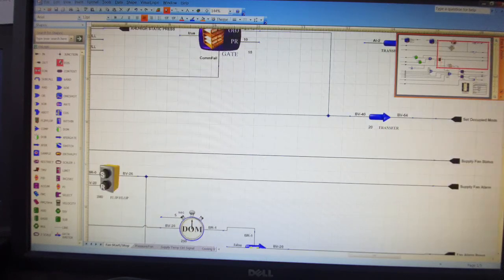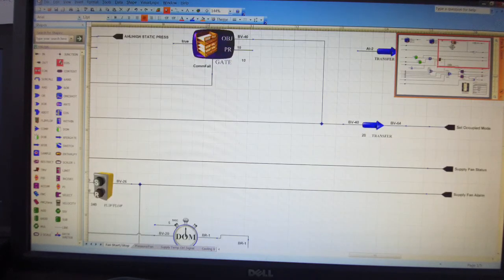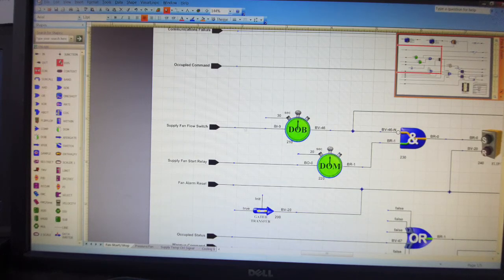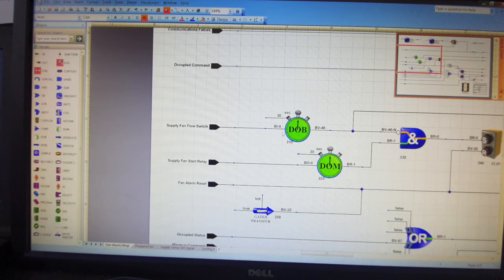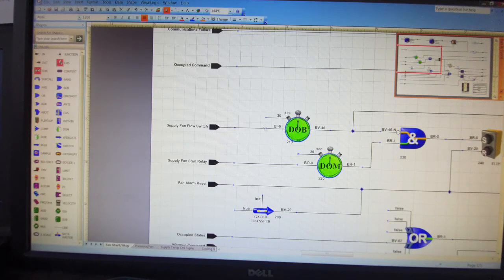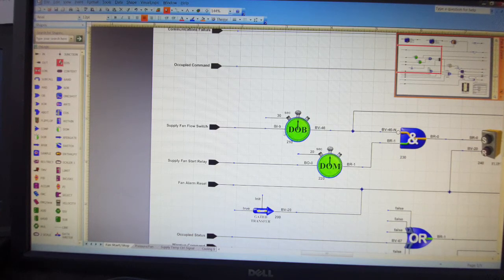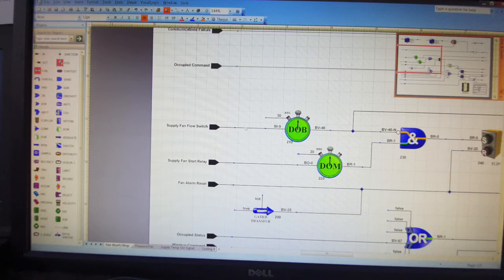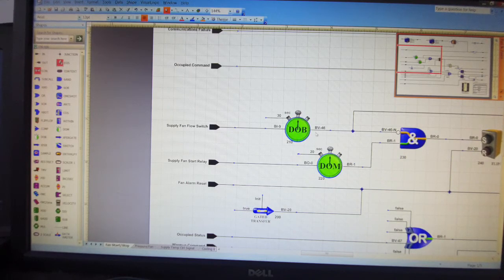We have to use the command BV40 to give the fan command. The fan switch status is binary input 9. This is physical input from the controller. Delay on break is the command, and delay on break is 30 seconds after the command. The output after 30 seconds is binary value 46.